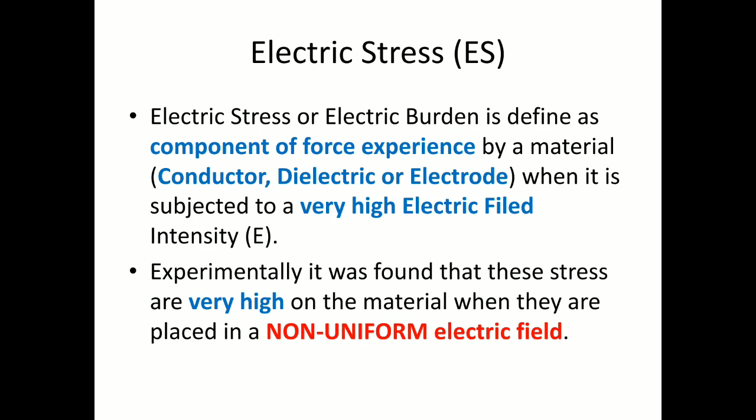And experimentally it was found that this electric stress is very high when the distribution of electric field is non-uniform in a given medium, which is very important. So the thumb rule is that if we want to reduce the value of electric stress on a given material, definitely our objective is to have a uniform distribution of electric field in that region.